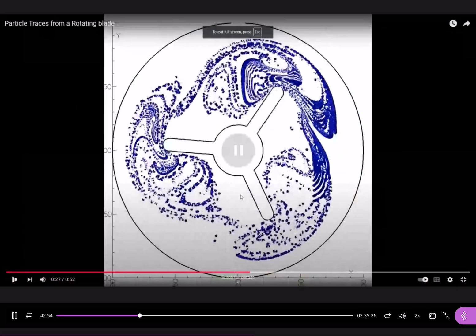Now, how do we do the calculations? Let's go back to this. Earlier I mentioned that when a rotating system is in operation, there are two types of noise effects: broadband noise and discrete noise. Discrete noise comes from the force created by the blades acting on air particles, so the ventilation system in operation may generate different frequency components.